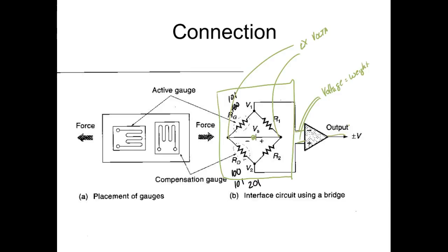These wires give us a voltage for weight, but we've got the weigh bridge over there. Let's say with the weigh bridge over here, on the output I get plus 5 volts. Well, what I do is just tell my scale that plus 5 volts equals what? Zero. We just zero it out. And there are still some functions I've seen even on digital indicators where you can zero things out.